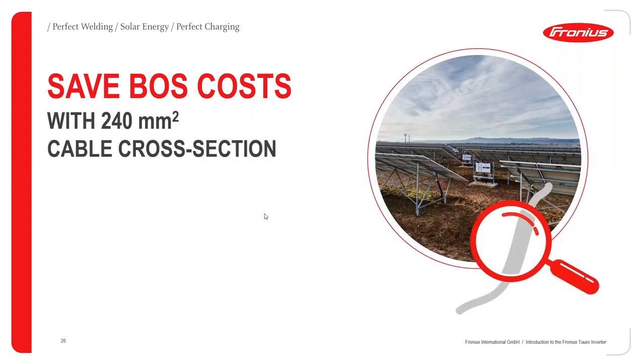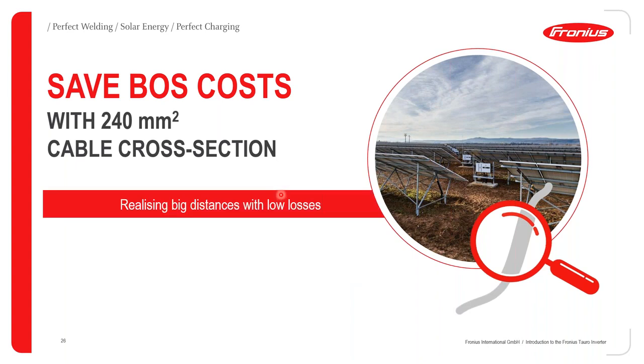Let's now continue looking at the BOS costs further, and how to save with 240 millimeter square cable cross sections. This is the biggest cross section, of course, that can be connected to the Tauro inverter. And this helps a lot when you are running the AC cabling for longer distances.